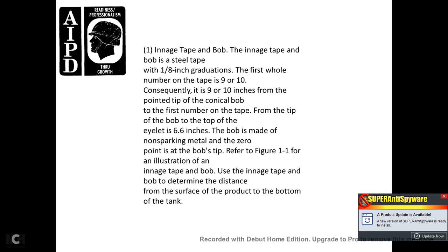11. The innage tape and bob is a steel tape with one-eighth-of-an-inch graduations. The first whole number of the tape is nine or ten, meaning it is nine or ten inches from the pointed tip of the conical bob to the first number on the tape. From the tip of the bob to the top of the eyelet is 6.6 inches. The bob is made of non-sparking metal with zero at the bottom tip. Refer to Figure 1 for an illustration. Use the innage tape and bob to determine the distance from the surface of the product to the bottom of the tank.